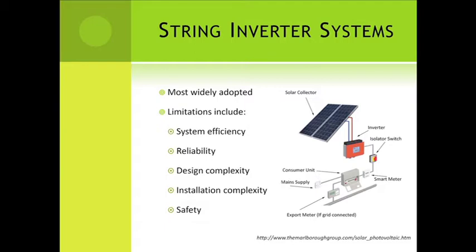Traditional string inverters are connected in series, so you have multiple solar panels connected in series. If one panel fails, the panels behind it are incapable of sending that current to your inverter, so the efficiency of the entire system goes down.